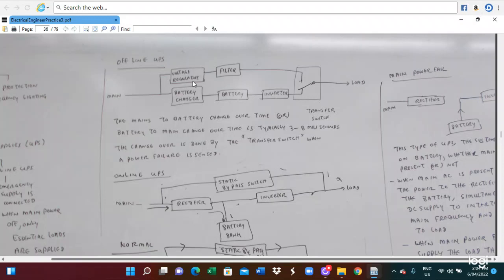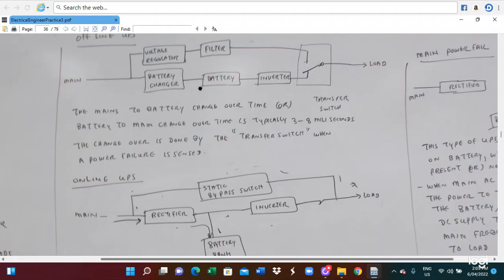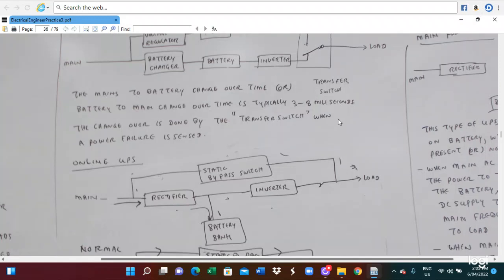The main power supply includes the voltage regulator and filter, connected to the load, and also the battery charger, battery, and the inverter. So the power is transferred from this side to this side. Then when the main power is off, the switch goes to the inverter and battery side, and the load continues to be supplied. When the main power is on, the battery is being charged. The changeover time from the main to the battery, or the battery to the main, is typically 3 to 8 milliseconds. Within 3 to 8 milliseconds, the power will be transferred. The changeover is done by the transistor transfer switch when the power failure is sensed. So when the main power fails, the sensor switch senses it and transfers to the battery side. By this way, emergency power is supplied.